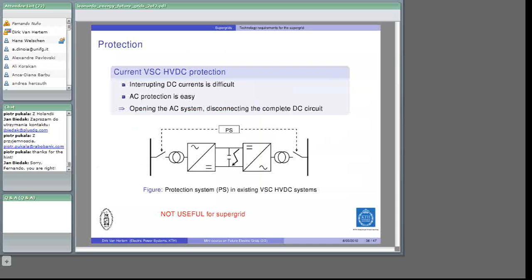There are some supergrid protection boundaries. First of all, if a fault happens in a DC system, the current rises very rapidly in all transmission lines, all DC lines that are connected. However, we need to be selective. Only the affected DC line must be switched. Another disadvantage of the voltage source converter, or maybe even DC systems, is that it's power electronics and it cannot withstand very high overloads for a long time. So it has to be fast enough. And this, of course, with no inductance to limit the current at all. And of course, we only want the protection system to operate in case that we actually have a fault, and not during any load change or an AC fault, or maybe a terminal that is disconnected, but not necessarily for a fault situation.